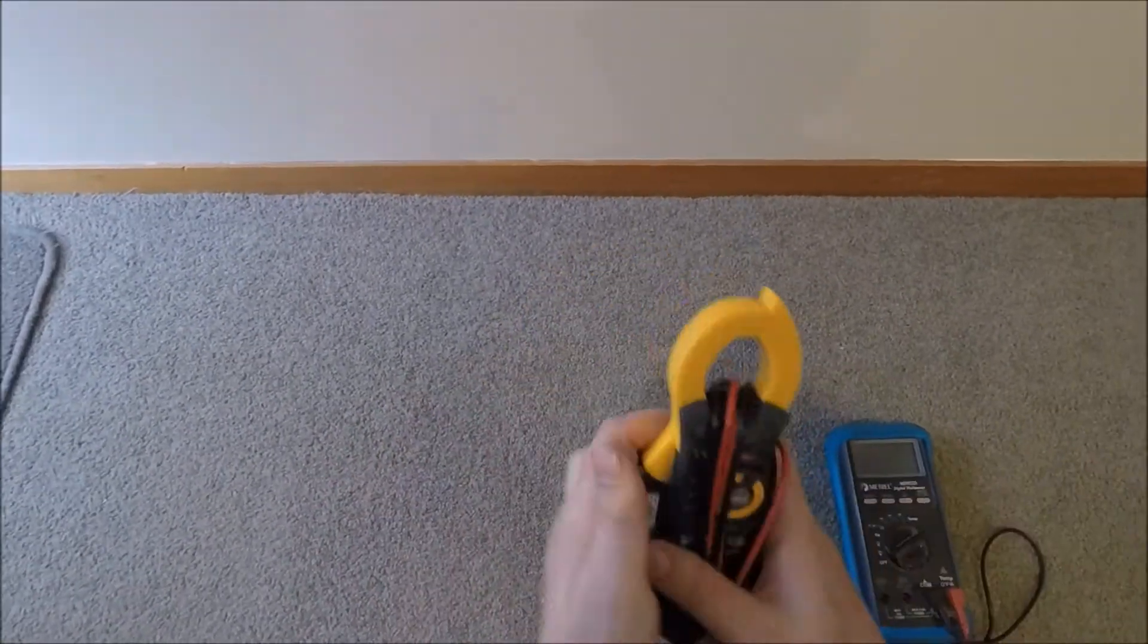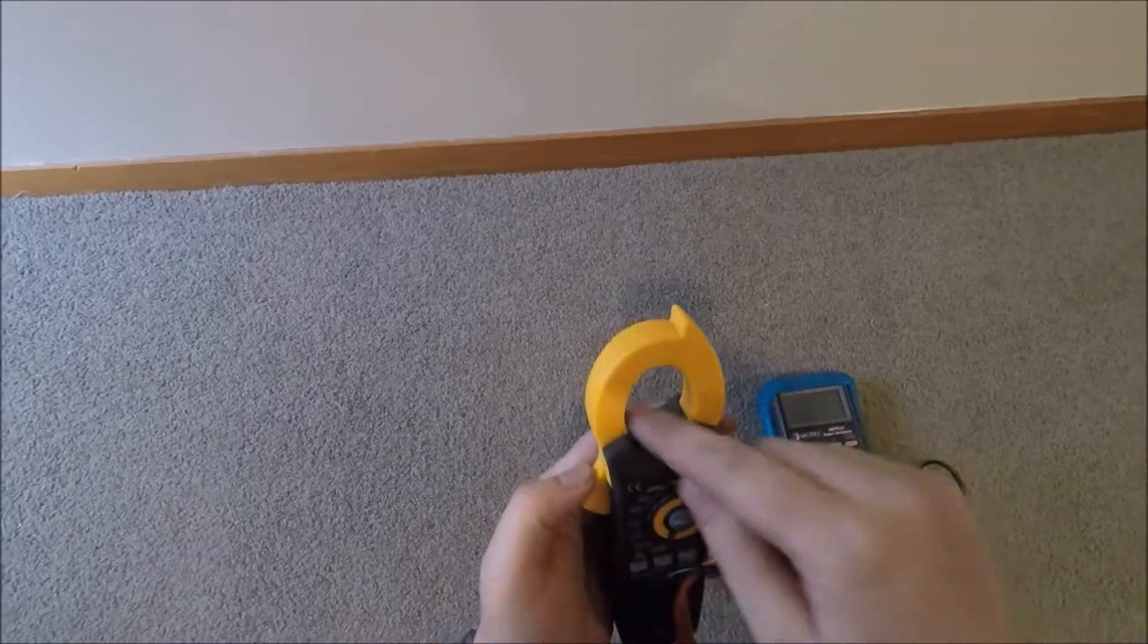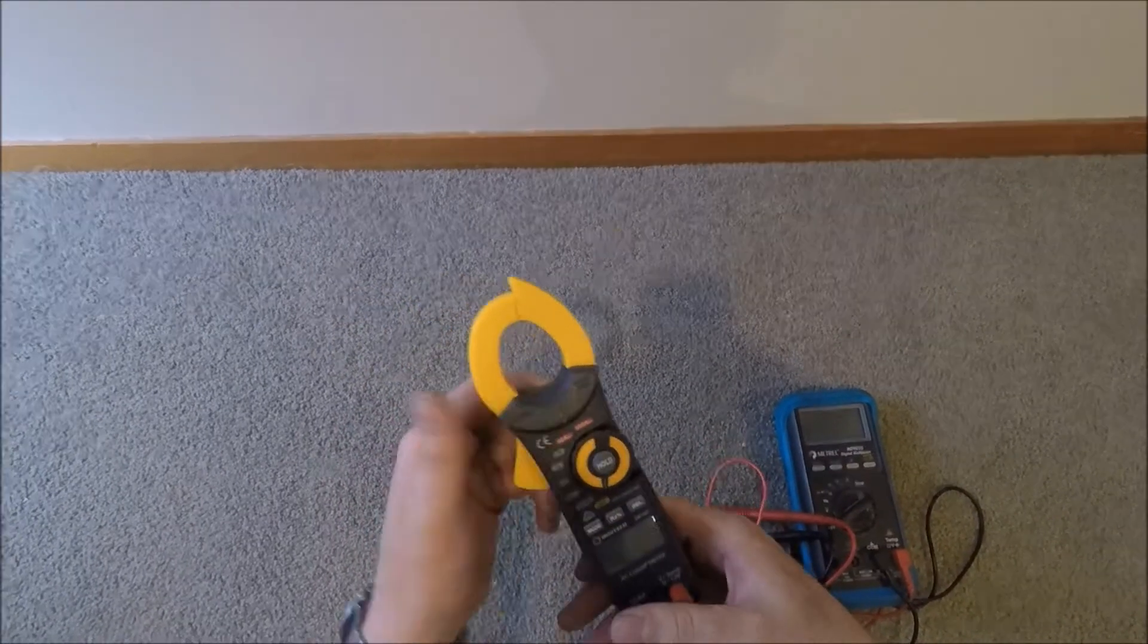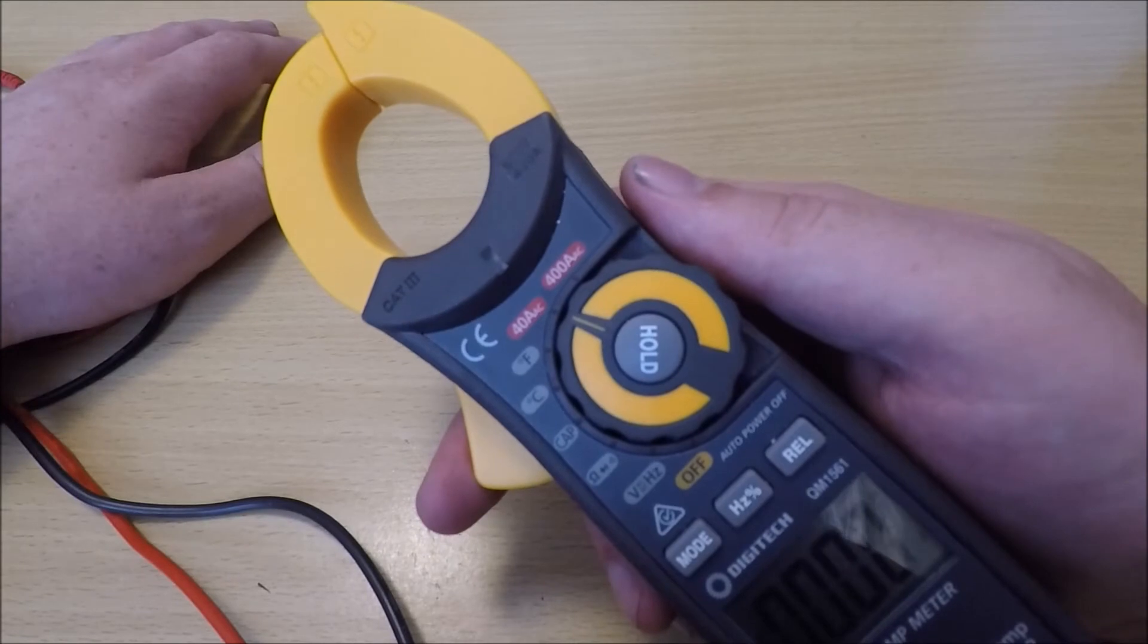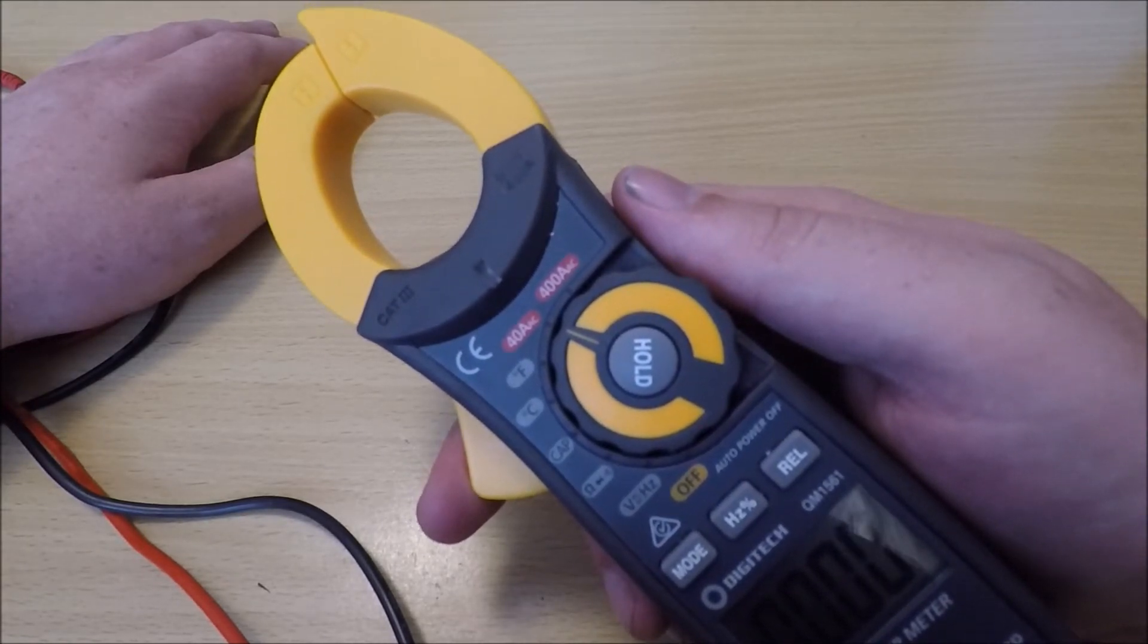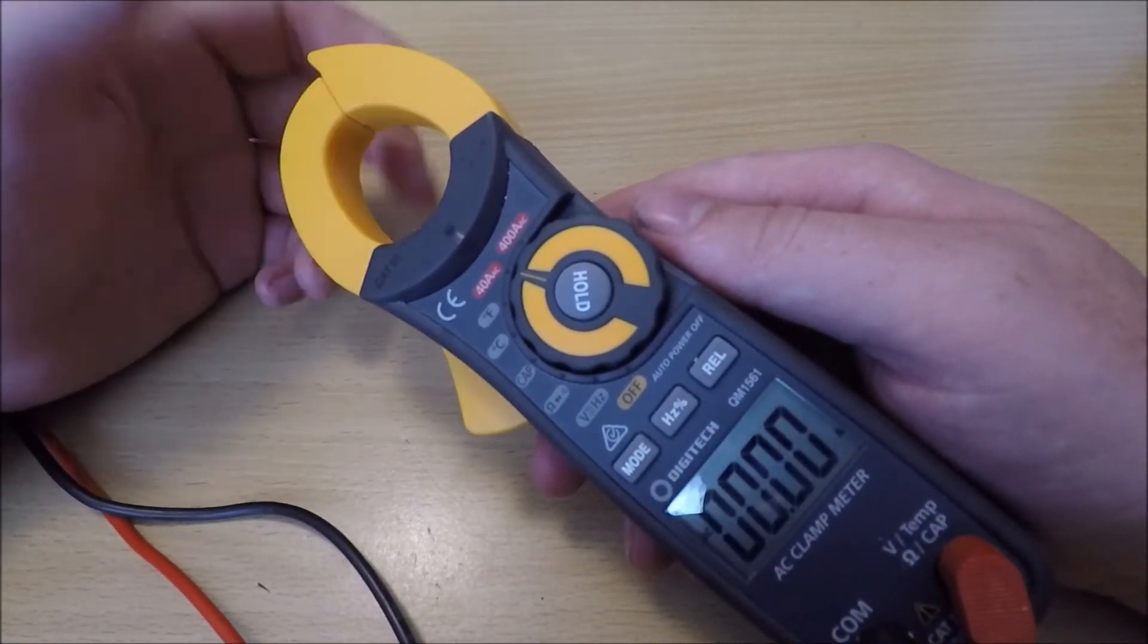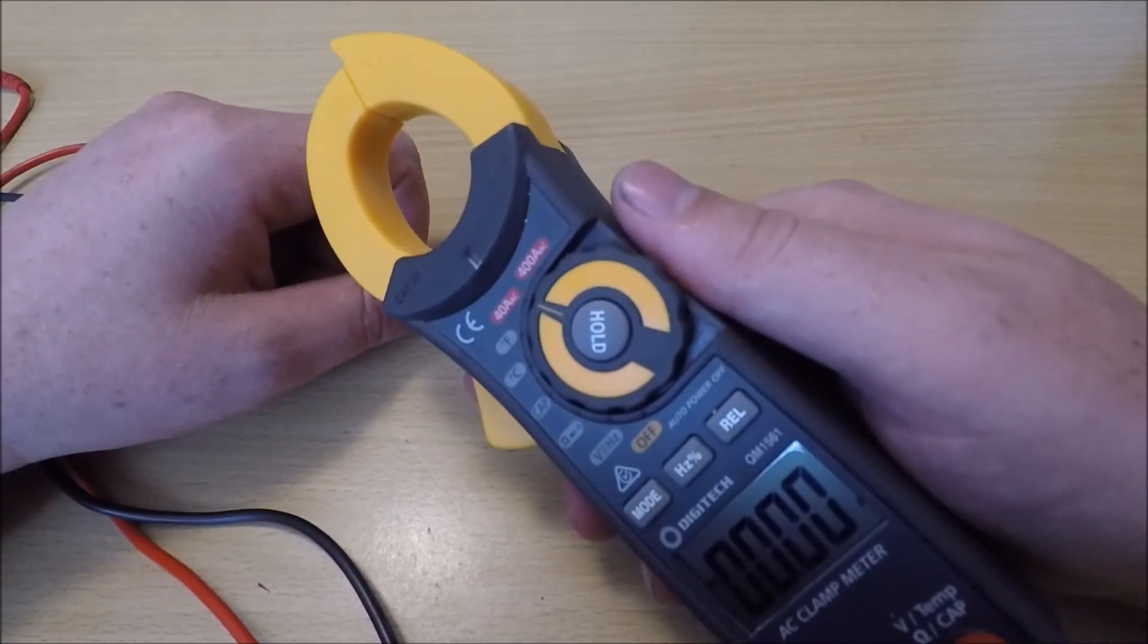That's the handy thing about these clamp meters. You can just clamp this end, this loop, around the cable and it will read how much current the circuit is drawing, how much load is being drawn through the cable. This is especially handy for doing towel rails, underfloor heating, and hot water cylinders where they've got elements that take a long time to heat up. If you want to test that they're working, you can put this around them, see how much current they're drawing straight away, and you'll know whether they're going to work properly.